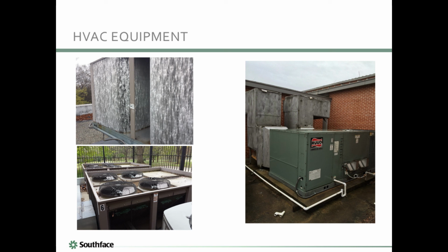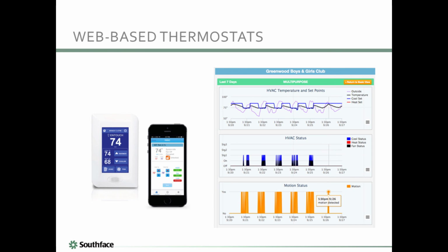The HVAC equipment in most of the recreation centers is unitary equipment, so split systems and package units, mostly with gas heat. Roughly 2/3 of the energy consumed at recreation centers is used for heating, cooling, and ventilation. Like most small commercial buildings, these were heated with unitary units. Most of the systems surveyed were less than 10 years old and in good condition. One exception is the photo in the top left showing some extensive hail damage. Most of the systems had gas heat with 80% furnaces. Cooling efficiency for most of these units was near the code minimum, though one building had 15 SEER equipment.